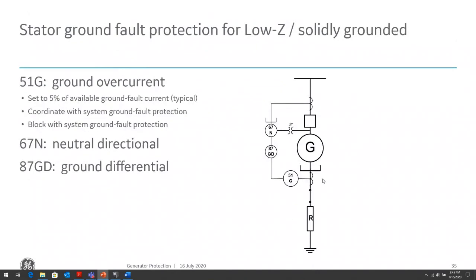So typical protection on a low impedance, solidly grounded system, you'll have a 51G ground fault, maybe even a 67N. We'll talk about why we might need a 67N in a slide or two, and maybe an 87 ground differential. Again, economics of scale here, obviously adding an 87 ground differential will require having another set of CTs to be able to wire into that differential. If you don't have a second set of CTs, then you might only be able to do a 51G.